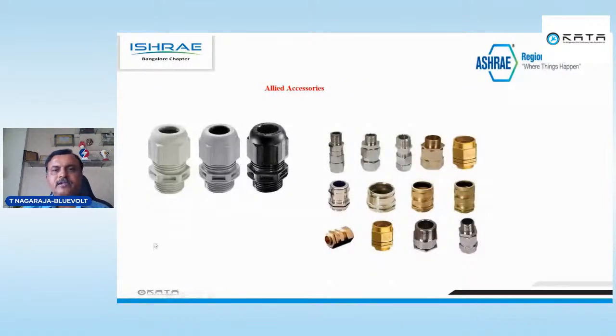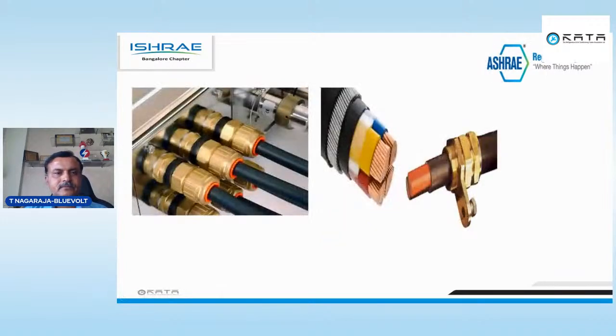These are the glands I mentioned. Whenever you are using armored cable, please go with brass glands. This is the PVC gland. Use it whenever there is only flexible cable or round sheathed cable with no armor. These brass glands are single compression, and these are double compression. Double compression and single compression glands. When used outdoors, double compression can be used, based on the customer specifications. This is a cable, just a pictorial representation to see.